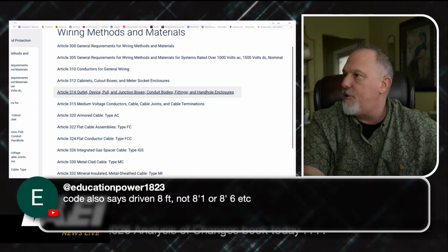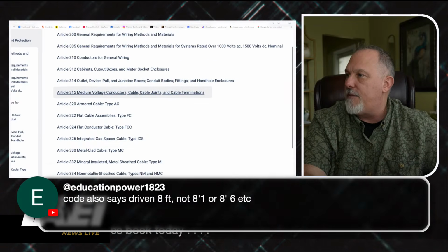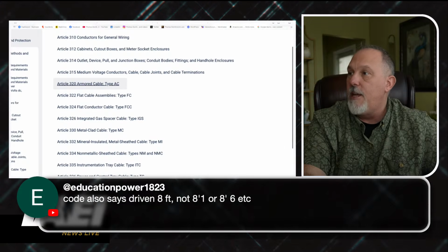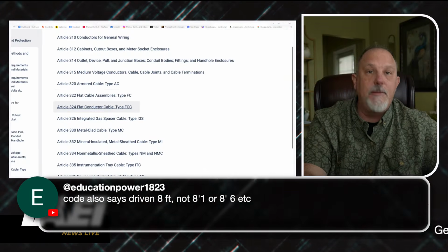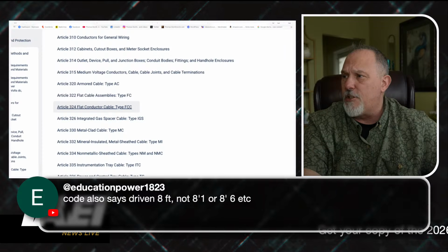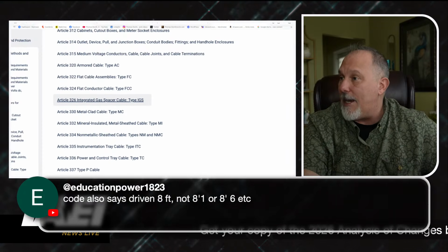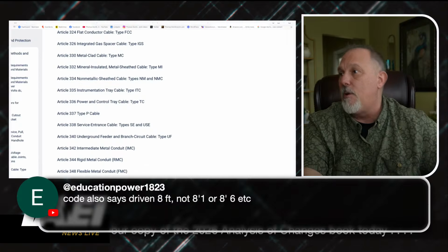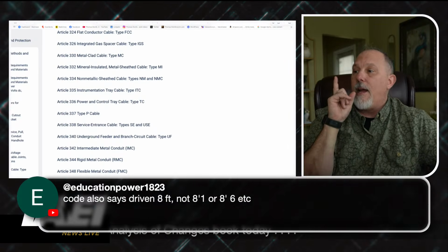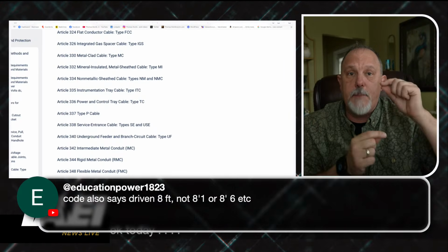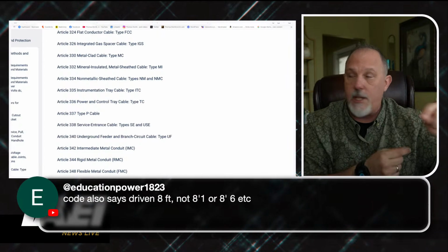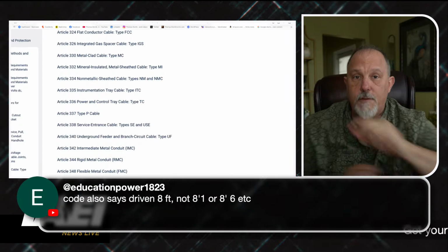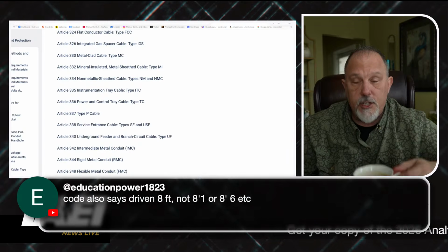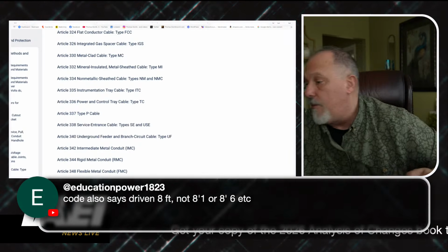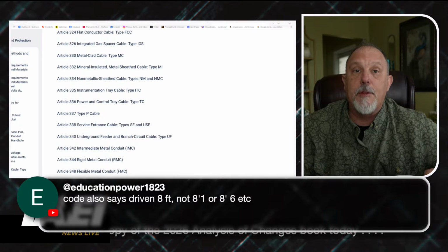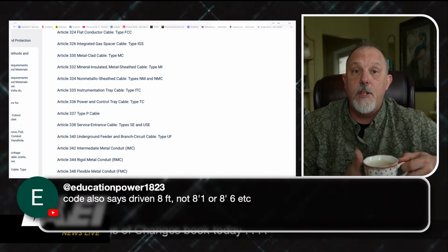You've got your cabinets and cutouts, outlet devices, medium voltage conductors. Then you've got all these different types of cables and cable assemblies: conductor cables, type IGS, MC cable, MI cable, NMC. I would say it's very important, depending upon the conductors you're using, to go to these articles. You'll find more information related to the proper application of the conductor you are applying.